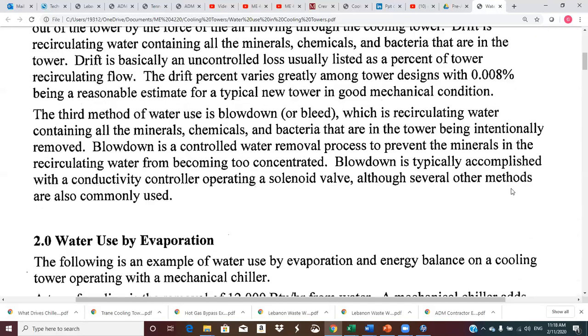And the third method is blowdown. Some people call it bleed flow, where in order to control the concentrations of minerals, chemicals, bacteria, that sort of thing, we intentionally drain some water from the tower, put it down the sewer, and then make it up with fresh water. That still has a little bit of at least the minerals and probably chemicals, hopefully no bacteria when it first comes in, to maintain the water inventory at the appropriate level.